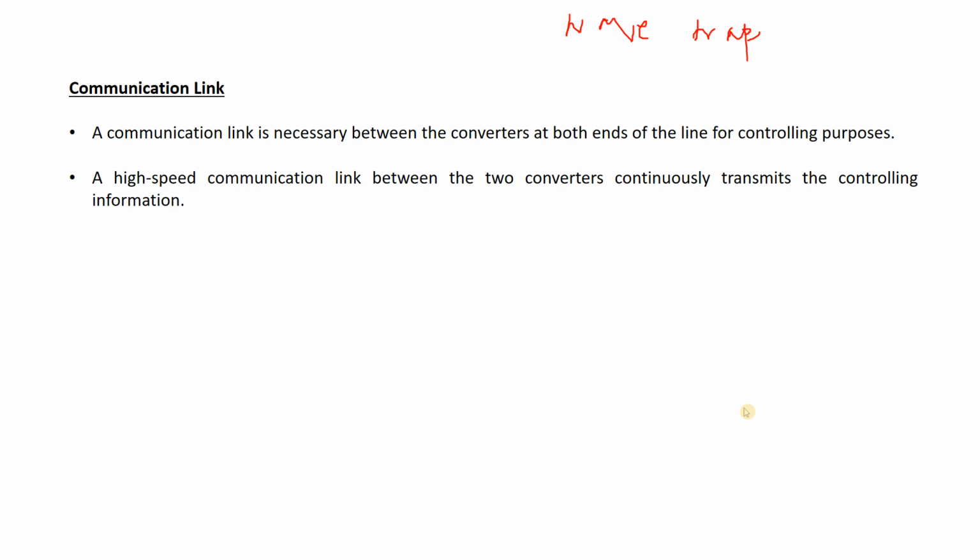So it has to be isolated. The wave trap is a frequency filter, just like a harmonic filter. It bypasses the frequencies of the communication signals and only allows the fundamental 50 Hz frequency to enter the substation. In that way, the high frequencies are bypassed and then connected to the offices for communication, for telephone.